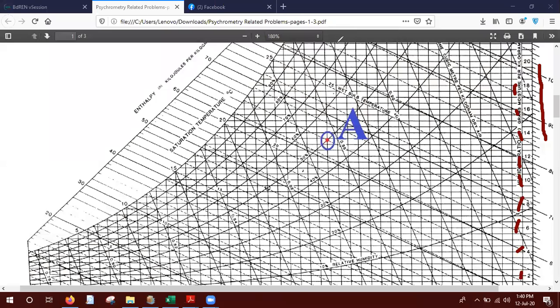So next, we need to find out the humidity ratio or humidity value. So this is a scale. We will draw a perpendicular line to that scale, and this will be the intersection. You see that this point is 12, this point is 14. In between there are 1, 2, 3, 4 stages, so every stage is 0.5. This is 12, so this will be 13, and our point is probably 13.5 or 13.4. If I'm drawing carefully, our point will be 13.4 or 13.5.